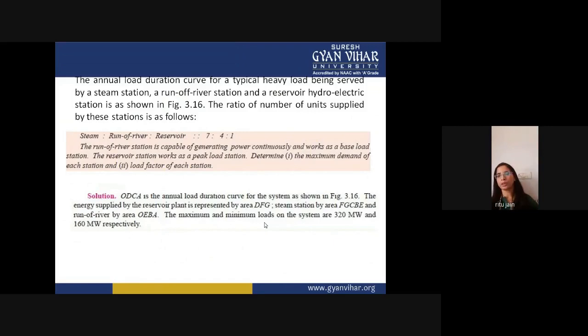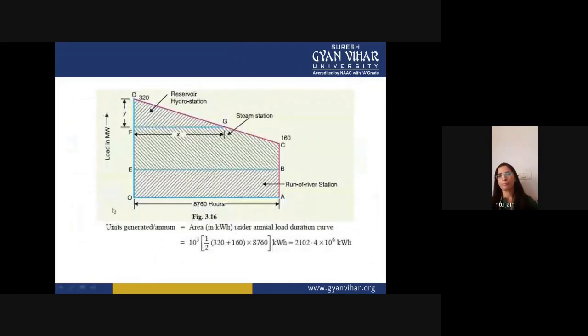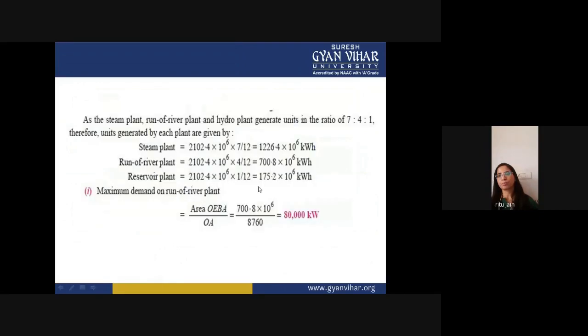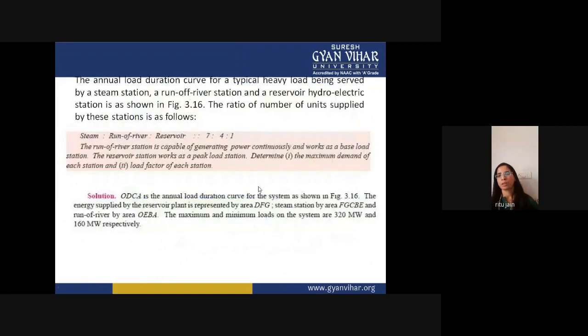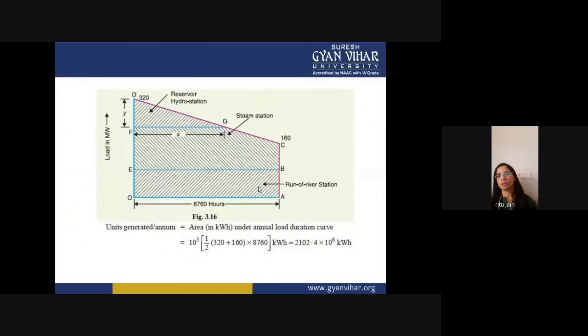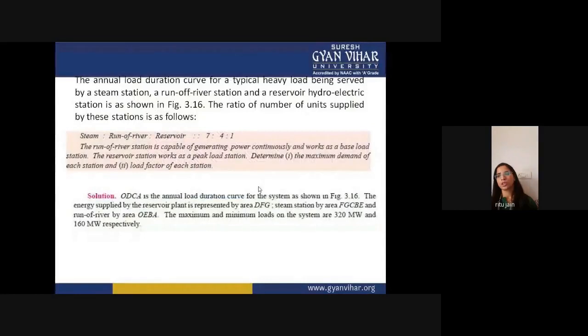So from the diagram you can see that ODCA is the annual load duration curve. This is your maximum demand. This is your minimum demand. This is your reservoir hydro station. This is your steam station. And this is your runoff river station. So the energy supplied by the reservoir plant is represented by the area DFG, and the steam station by the area FGCBE and the runoff river by the area OEBA. And the maximum and minimum loads are 320 megawatt and 160 megawatt respectively.